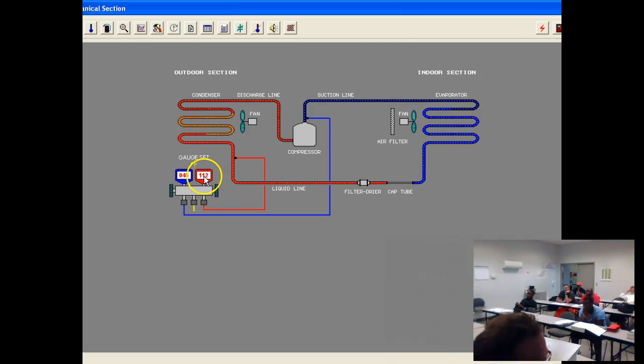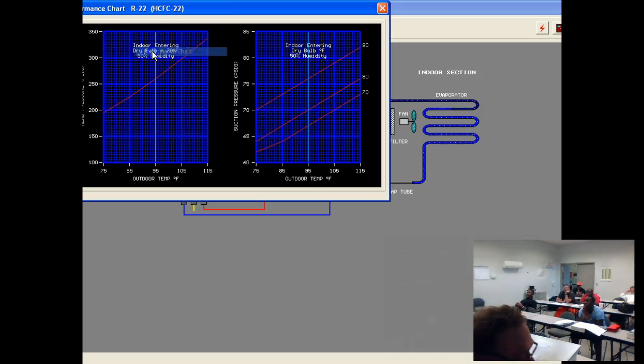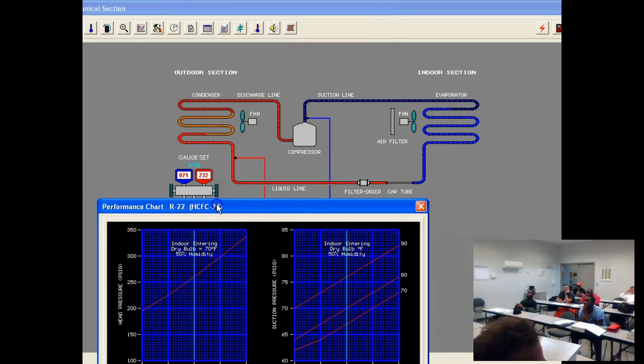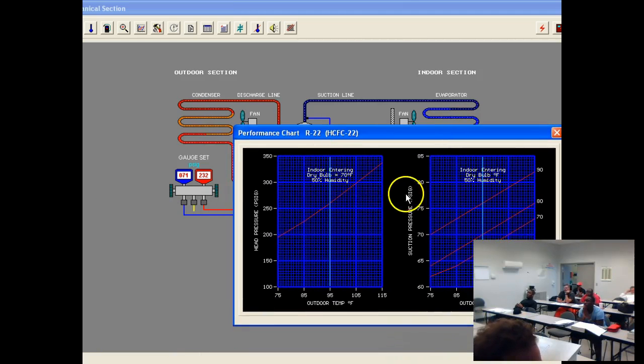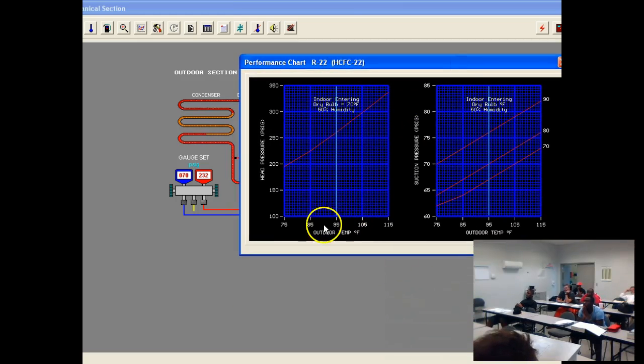My pressure here, well, my temperature, pardon me, 232 and 79. That's kind of different from last time, isn't it? If I pulled up my performance chart, put it over here. If I pulled up my performance chart, 71 doesn't seem that bad, but 232 is definitely low. Let's see, 95-degree day. If it were 70 degrees inside, which it's 85, should be a minimum of 260, maybe 280. We're at 230. So there's another symptom. I got low head pressure. Okay? So let's go take a look at that.